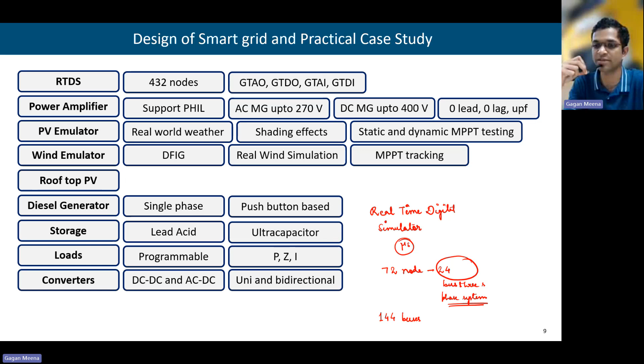But for testing a digital, let's say numerical relay or some protection equipment, we don't require this power amplifier. If they need a signal of up to 10 volts, then we can avoid the power amplifier and simply boost the 5 volts to 10 volts and use it. A simple voltage boost of twice the order is sufficient here. That's why for operating real power equipment, we require a power amplifier. And it supports power hardware in the loop.